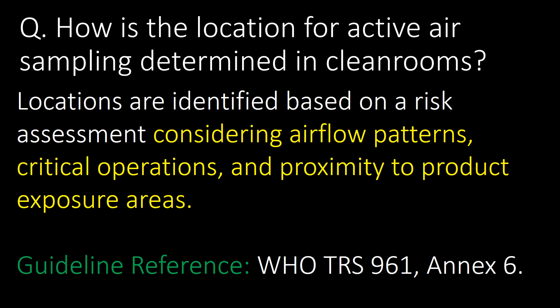How is the location for active air sampling determined in clean rooms? Locations are determined based on a risk assessment considering air flow patterns, critical operations, and proximity to product exposure areas. Guideline reference: WHO Technical Report Series No. 961 Annex 6.